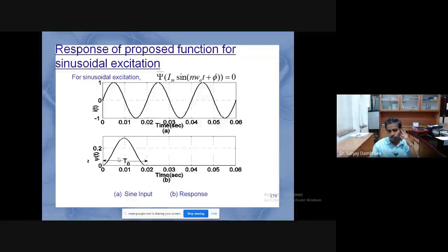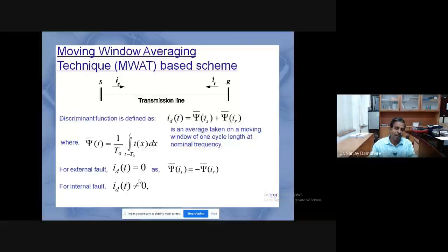If there is no fault on the transmission line, this signature and that signature will be the same, so the discriminating function will be zero. But if there is a fault, the discriminating function will be non-zero, and that non-zero value can be used for identifying the fault. This scheme is then tested for performance under various conditions - internal fault, external fault, and other disturbances - and that is how a more sensitive and more effective scheme can be seen.